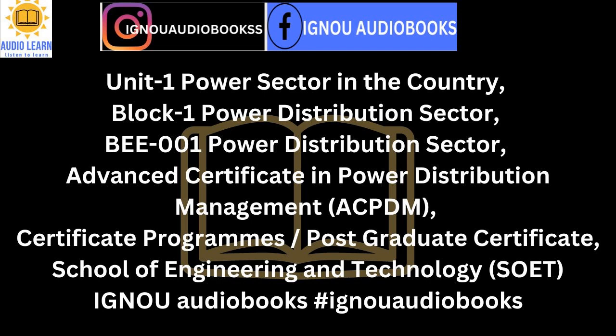The transmission and distribution network includes substations, lines and distribution transformers. Substations, containing step-down transformers, reduce the voltage for distribution to industrial, commercial and residential customers. These substations and distribution lines are referred to as the distribution system. Transmission lines are usually capable of transmitting large quantities of electrical energy over long distances, and they operate at high voltages. Distribution lines carry limited quantities of power over shorter distances.